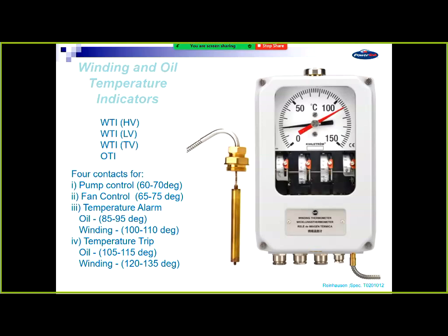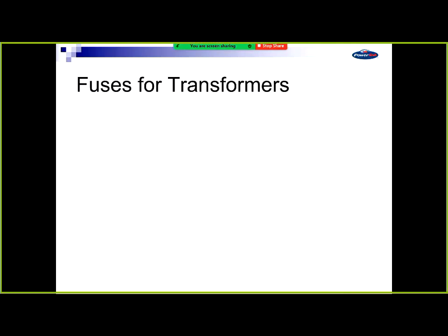There are winding and oil temperatures in there. Winding you'll see is higher, and that's because that's where the current's going through. That heats up quicker, but it takes time for it to get through the oil to heat up the oil. The oil is going out into the vents and fans, so they're cooling it down, coming back in. That's why you see the difference between the oil and the winding temperature. They're sort of guidelines. Different utilities will do that at different temperatures. I don't even know our standard temperatures. We just have a standard temperature where we set all of those, and that's in these devices, and we never change them, to be honest. It's been working for a long time.